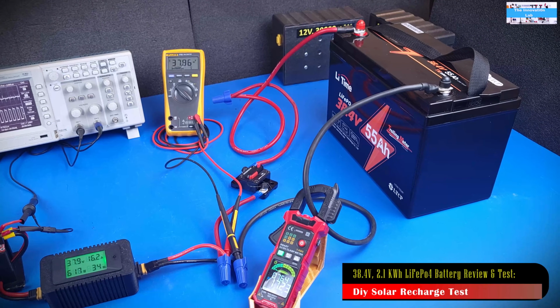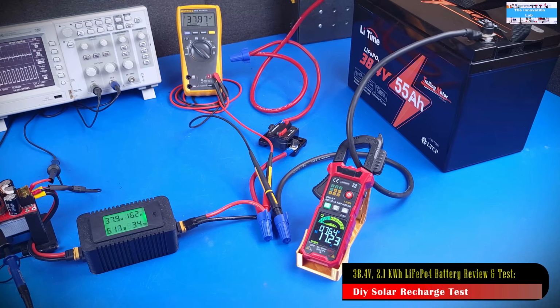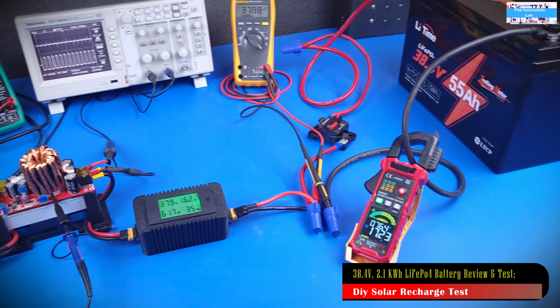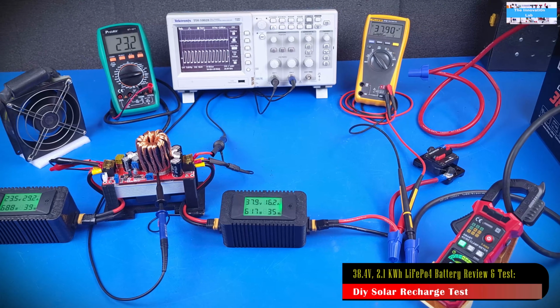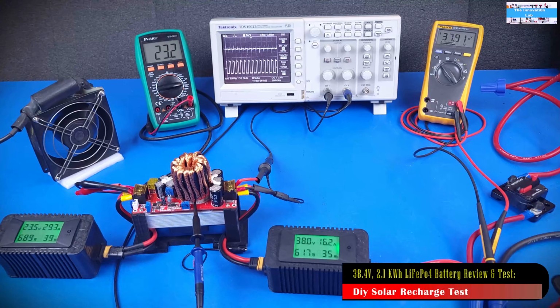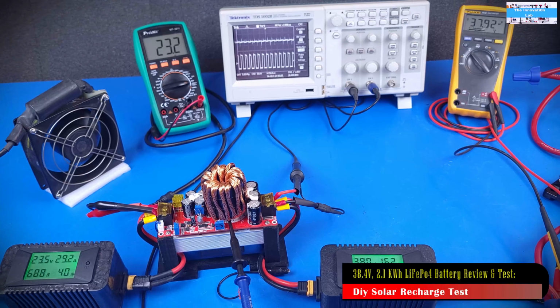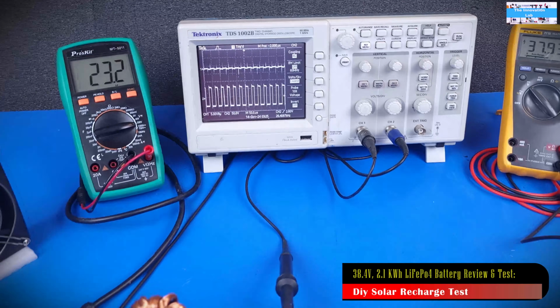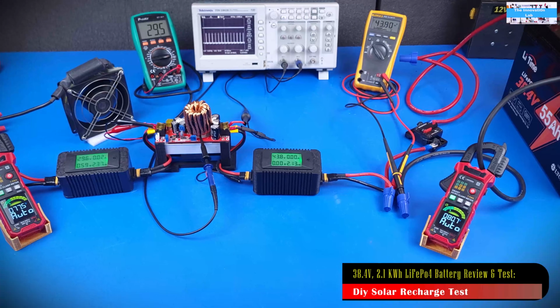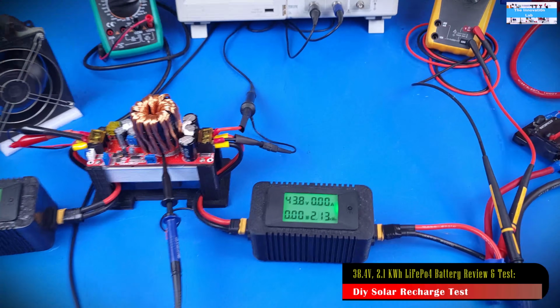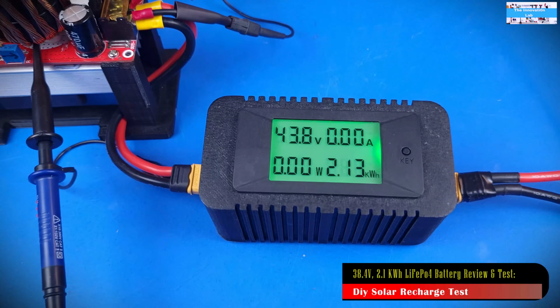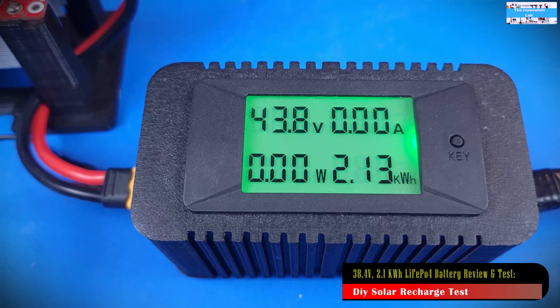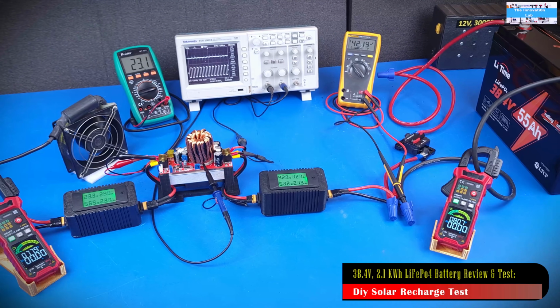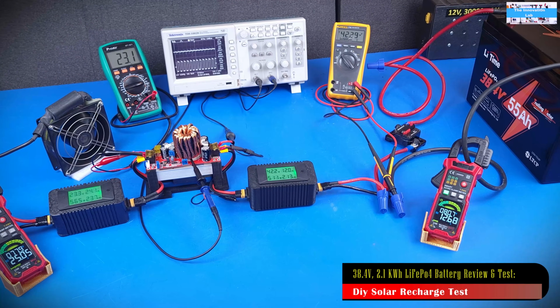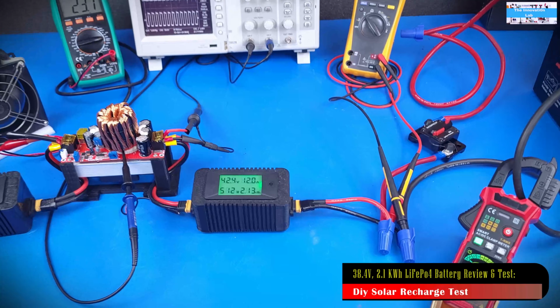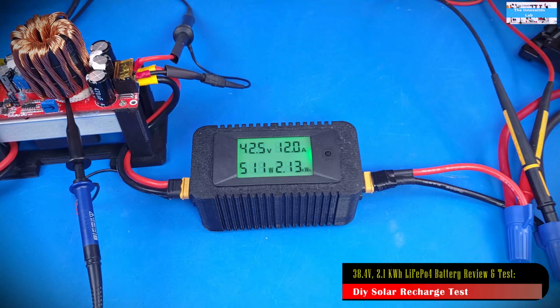At this point all we really had to do was leave the battery to charge, but we kept an eye on it to make sure everything was running well. We kept a fan on the system cooling it, and about 4 hours later the battery got to 100% SOC, meaning it's fully charged. At this point the BMS actually disconnected the battery system from the charging system, which is a great safety feature to prevent the battery from overcharging.